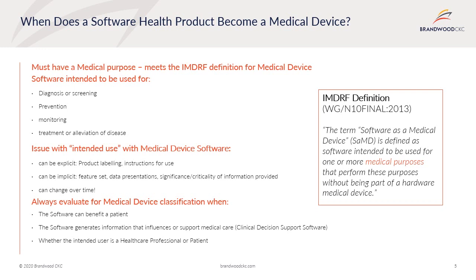The regulatory or market authorization process includes classifying the software based on the risk to the patient. The information used to evaluate classification and whether the software is a medical device should take into consideration how the software can benefit a patient, if the software generates information that influences or supports medical care — also known as clinical decision support software — and whether the intended user is a healthcare professional or patient.